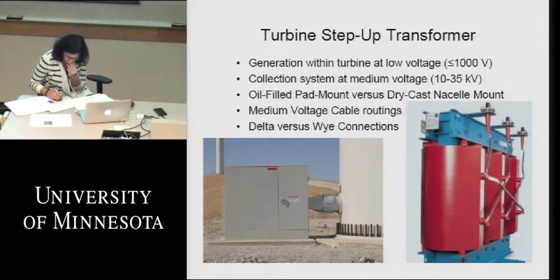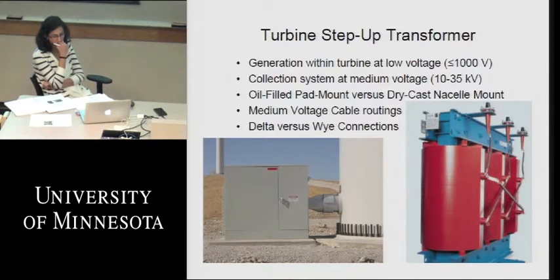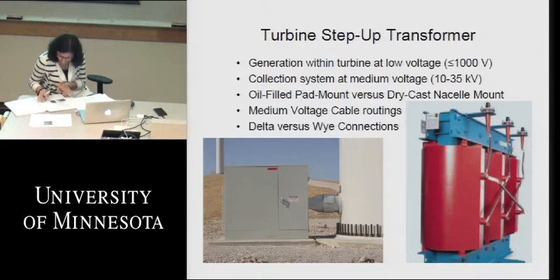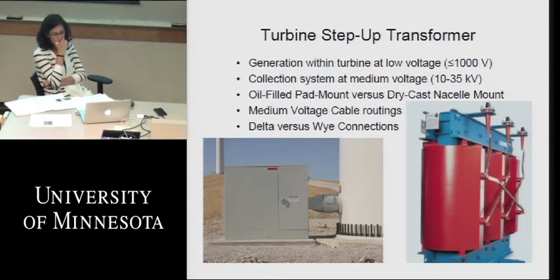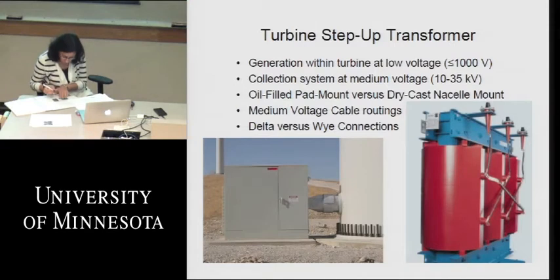If we do a pad mount transformer at the bottom of the tower, as shown on the left, then we've got to bring that full, say, 1,500 amps down, with multiple cables. So you've got the arrangements you have to make for suspending such cables over several hundred feet. That's a lot of weight, and you've got to keep the cables separated for proper clearance. So your suspending and cable handling arrangements are much more difficult if you use the pad mount transformer. But you can easily change the size of the pad mount as you like, or buy conventional distribution transformers instead of the dry cast transformers that we as manufacturers would probably supply, which are already in the nacelle when you get them on the site.